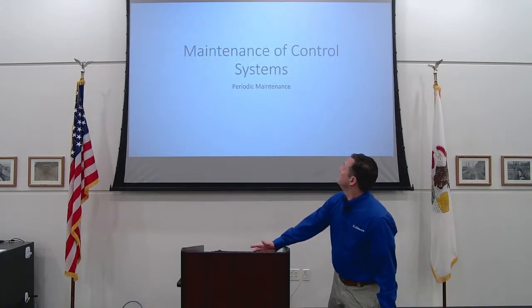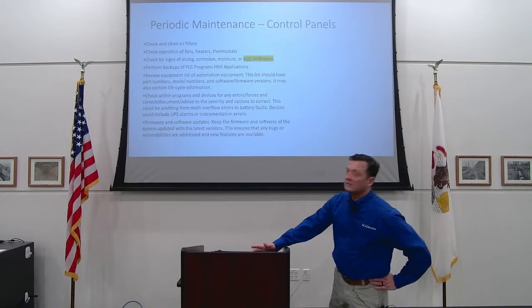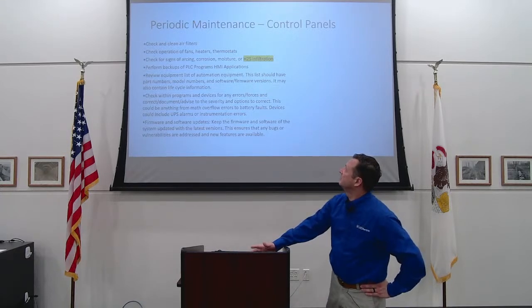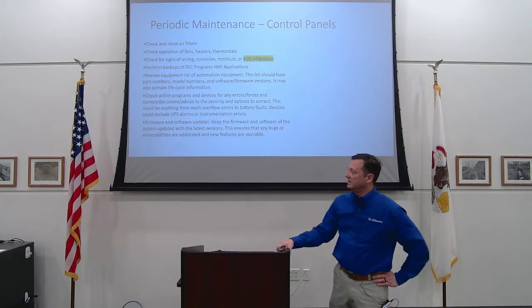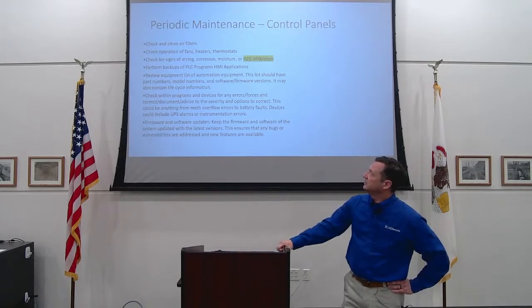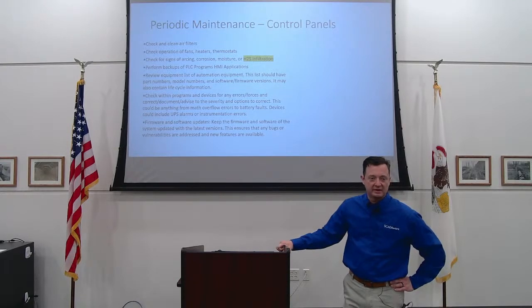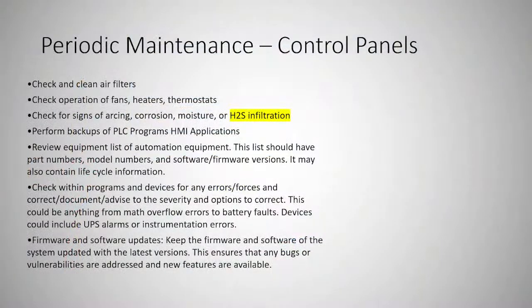I'm going to blow through some of this, but this presentation will be available. This is just some recommendations for periodic maintenance on all your systems - for control cabinets, making sure you're keeping backups of PLC programs, checking and cleaning air filters, making sure things aren't running too hot. But the highlighted item here, H2S infiltration, is something really important to watch for, especially at wastewater plants.